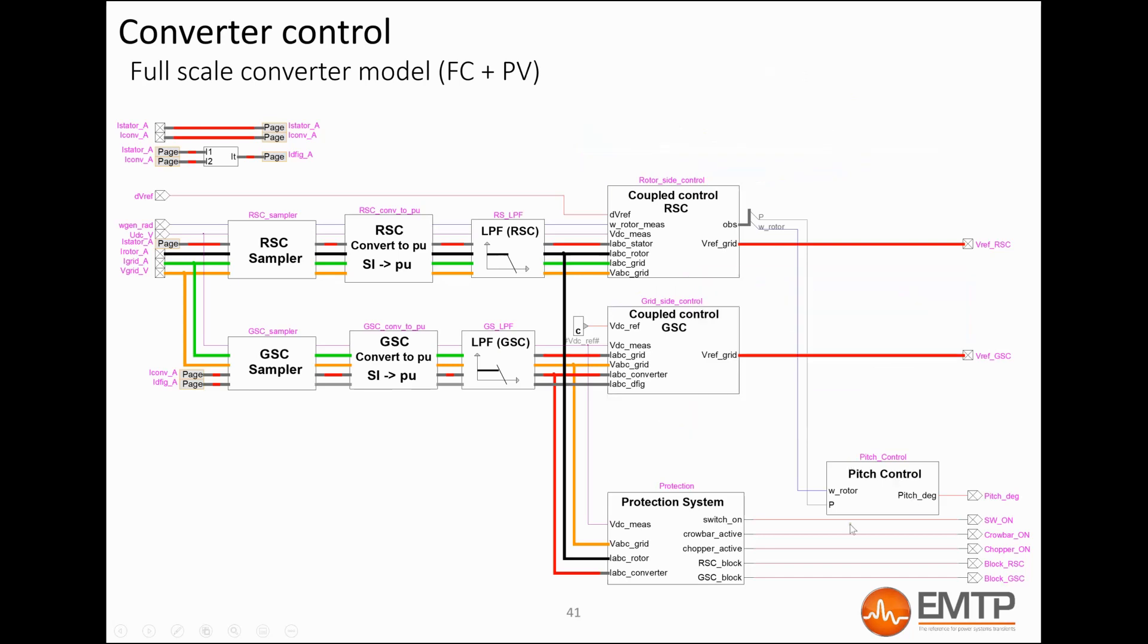The pitch control block limits the mechanical power extracted from the wind by increasing the pitch angle when the wind speed is above its rated. The protection system block contains cut-in and cut-off speed relays, low voltage and over voltage relays, machine side converter and grid side converter overcurrent protections, and DC resistive chopper control. The LVRT and OVRT functions are in this block.